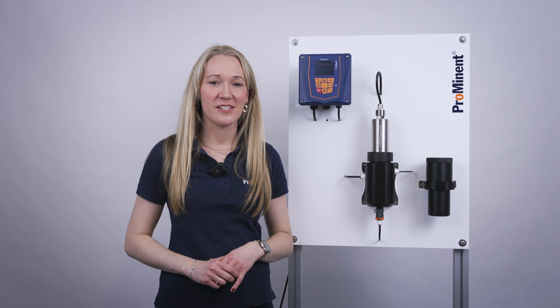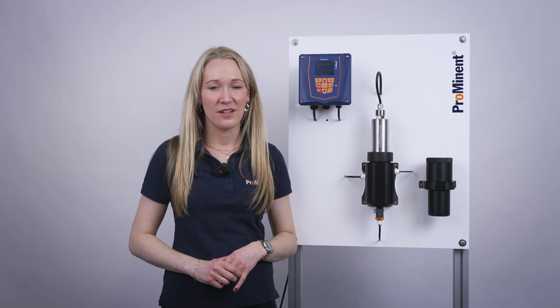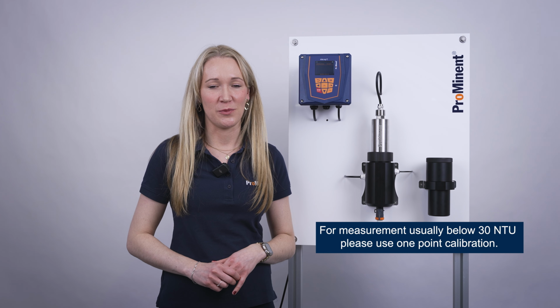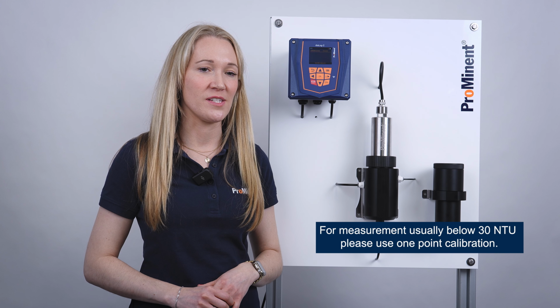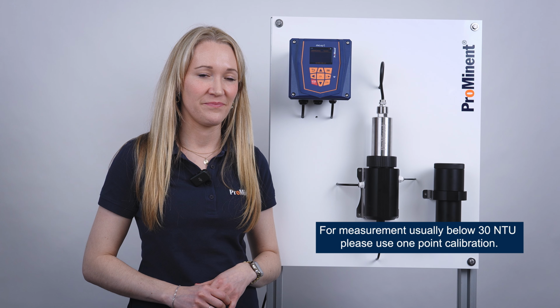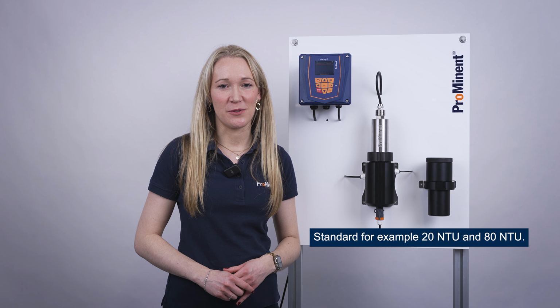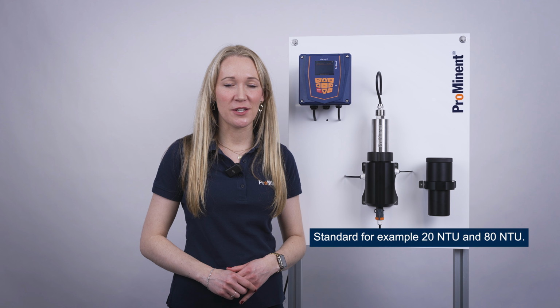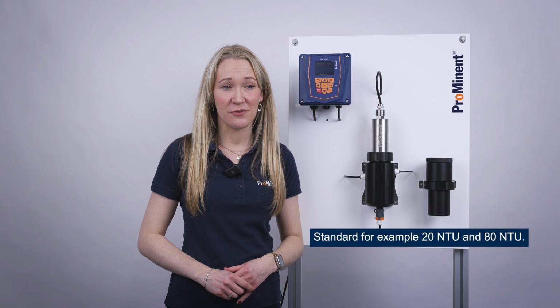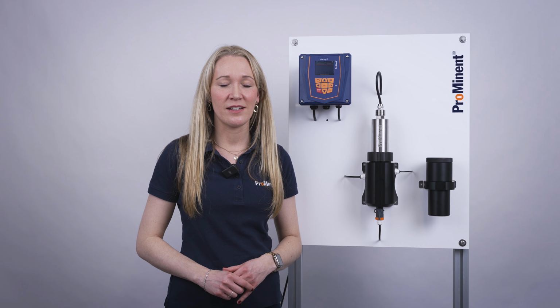For measuring ranges that are smaller than 30 NTU, in general we recommend a 1-point calibration. Therefore you choose a standard that is below 30 NTU. If you use the whole measuring range between 0 and 100 NTU, we recommend a 2-point calibration with, for example, 20 and 80 NTU. If you have a certain value that you expect, we recommend to use a 2-point calibration and calibrate directly above and below this expected value. Therefore you get a better precision.